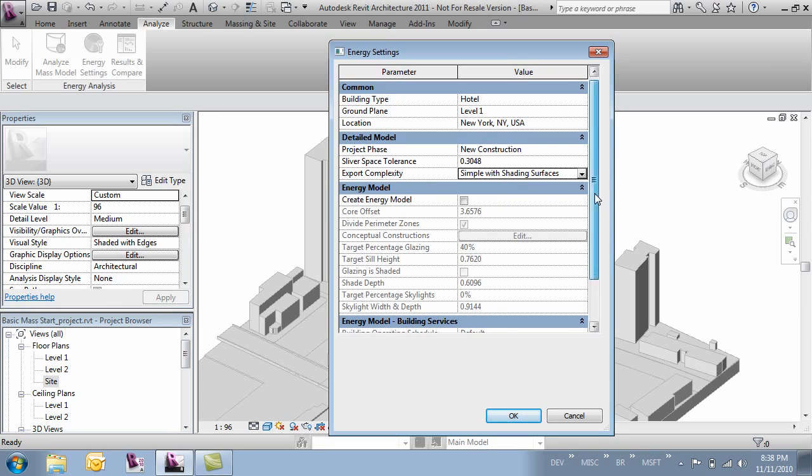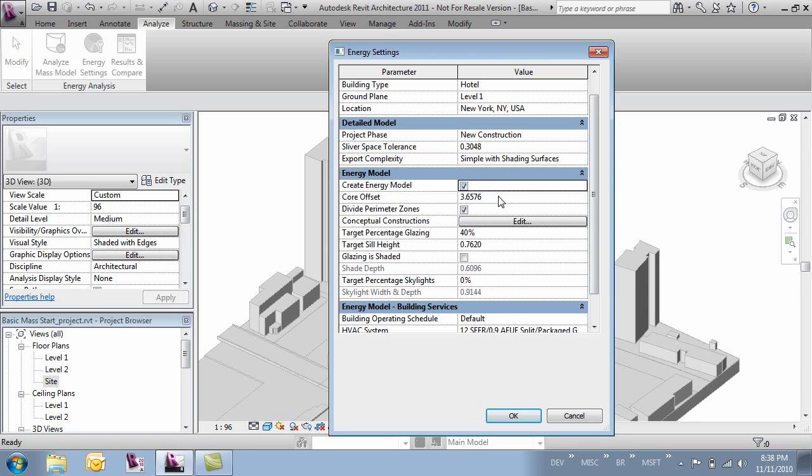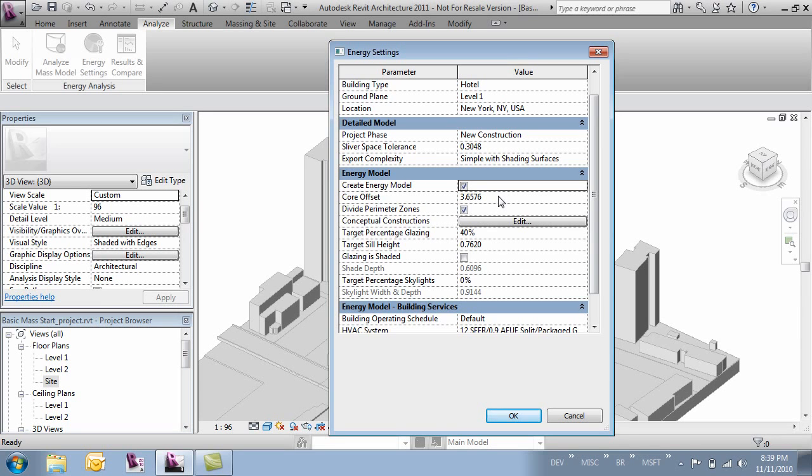Next we want to create an energy model. So we'll click this check box. And this first parameter is core offset. One of the things the energy model does for us is build a simplified mass that we can analyze. And by telling it how big the core is or how far offset we are from the face of the building to the core, it'll make that void for us. So let's go ahead and tell this to be 6 meters.